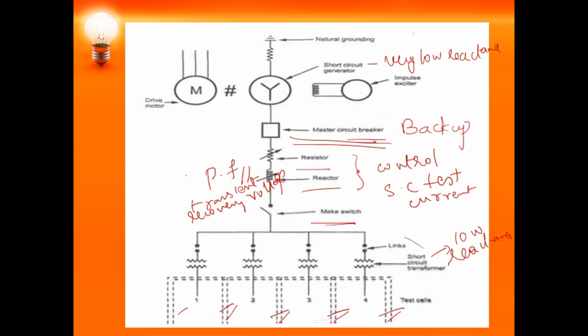So what is the testing procedure? How exactly are you going to test this? First the motor is driven. The motor drives the short circuit generator to a certain speed. The motor will make the generator rotate at a certain speed. After that, this motor will be switched off. Clear? That is the first step.